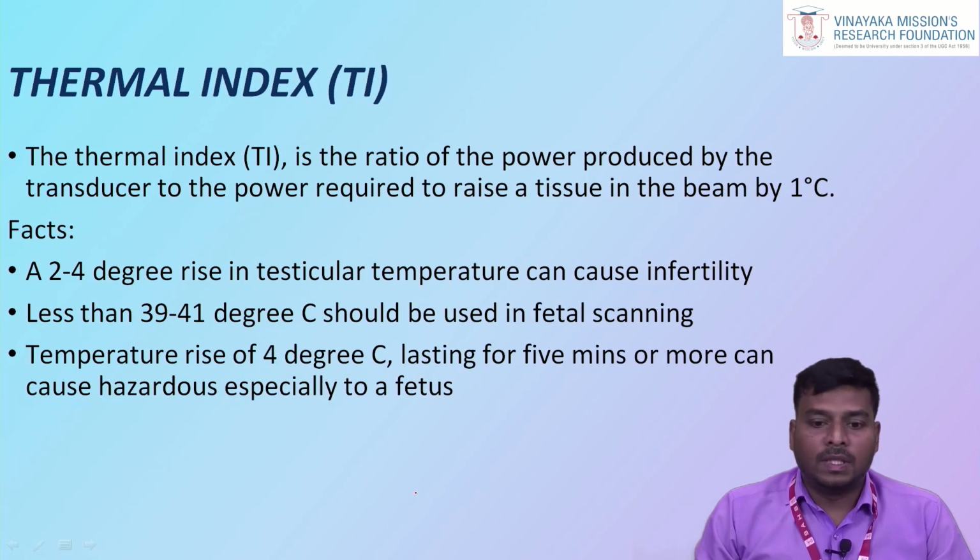Next, thermal index. Thermal index is the ratio of power produced by the ultrasound transducer. The transducer device sends ultrasound to the human tissues, then the echoes are reflected and received again by the ultrasound transducer. Facts: a 2 to 4 degree rise in testicular temperature can cause infertility. Second fact: less than 39 to 41 degrees should be used in fetal scanning. A temperature rise of 4 degrees lasting for 5 minutes or more can cause hazards, especially in fetal scanning.